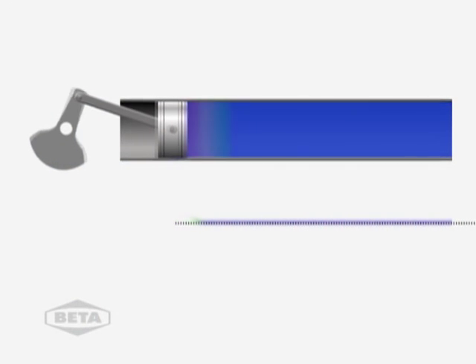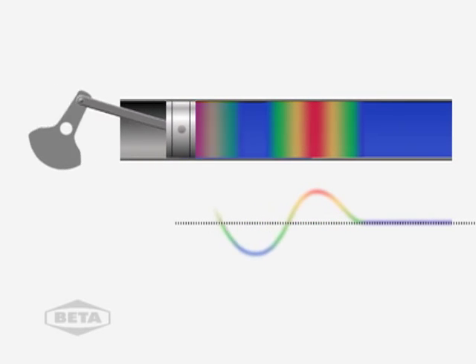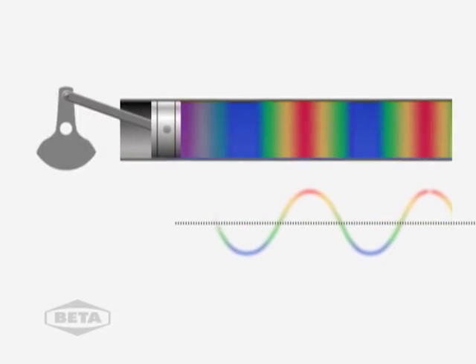As a piston moves forward, it pushes the gas or fluid ahead of it, which increases the pressure at the face of the piston. This creates a high pressure area that propagates at the speed of sound throughout the system. This animation illustrates the formation of pulsations. Like a ripple in a pond, the waves continue to travel away from the source, except with pulsations, they travel at the speed of sound in the fluid.